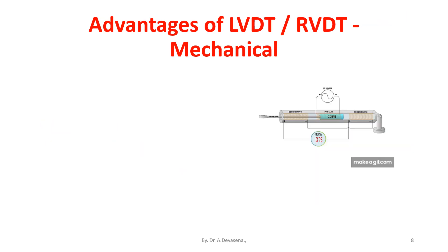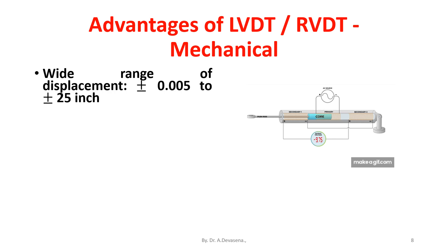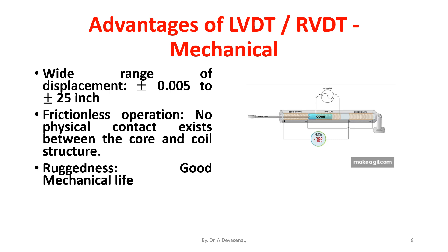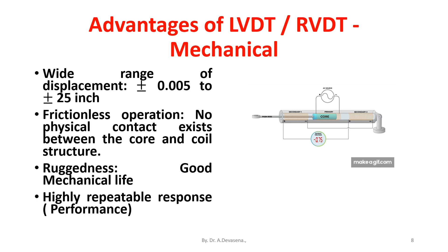The mechanical advantages of LVDT include: a wide range of displacement from plus or minus 0.005 to plus or minus 25 inches; frictionless operation with no physical contact between the core and coil structure; ruggedness and good mechanical life; insensitive to temperature changes; and highly repeatable response and performance.